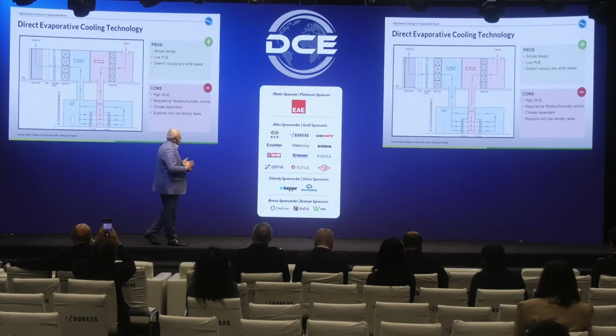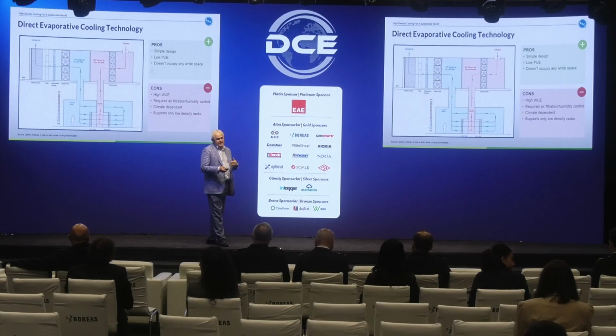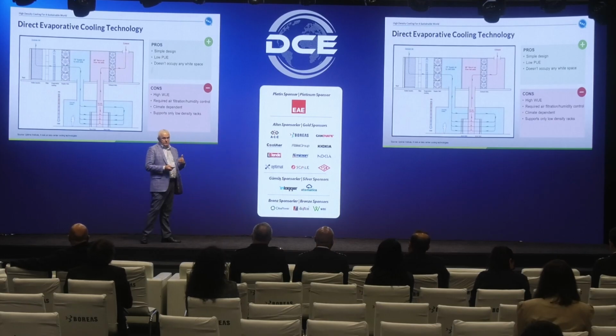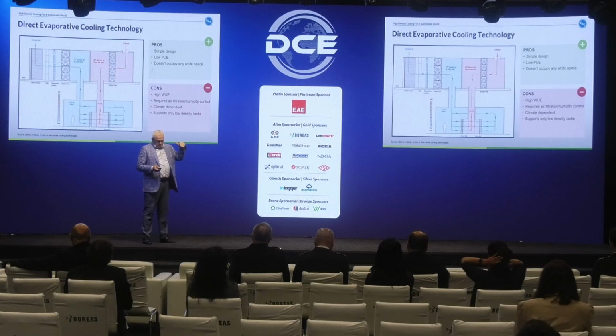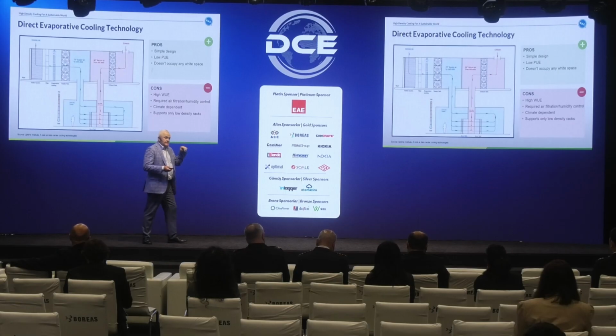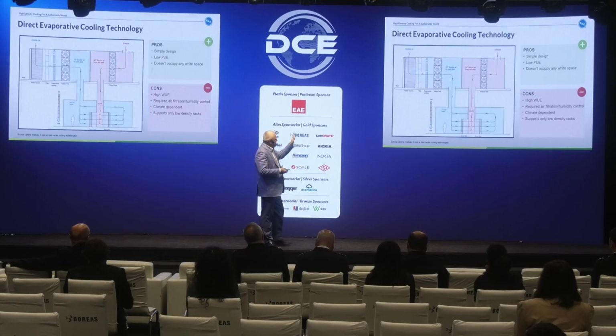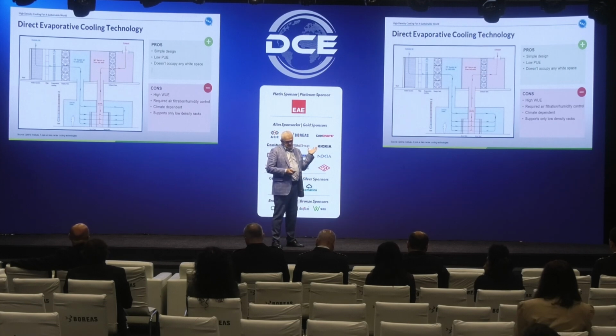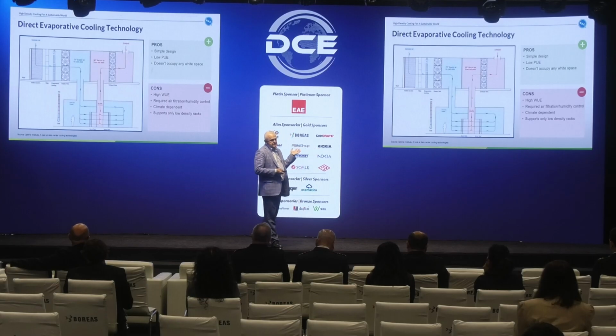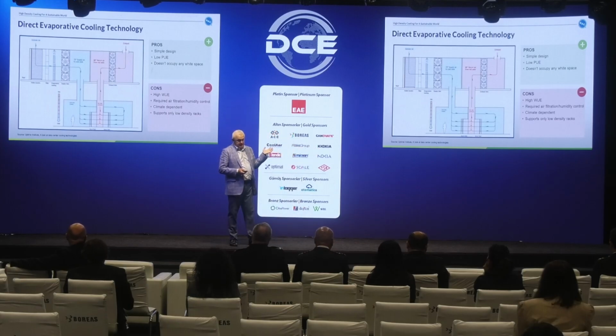So we have direct evaporative cooling, which is a big box on the roof of the building. Most of the time, it's a ventilation project. You bring fresh air into the building, go through the cold aisle, through the racks, and exhaust it through the hot aisle. In the summer, there is an evaporative media that gets wet and cools down the data center. It's very simple, and a classic cloud provider has used this basis of design for the last 8-9 years. It gives an extremely low PUE, a very efficient data center.